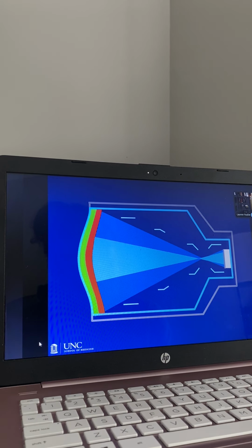It's not going to be bright because we have lost all of these electrons around the periphery here. So what the system has to do is increase the exposure to account for losing exposure on the periphery. We need to maintain the image brightness. So the downside to magnification mode is that patient exposure will increase. Patient exposure increases to have enough brightness.